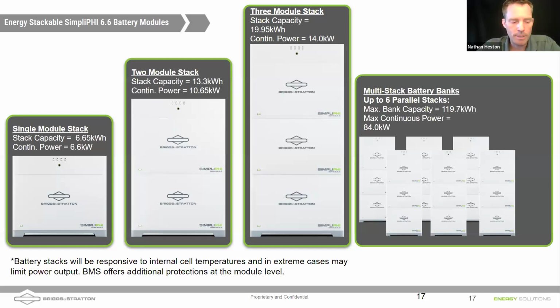Yeah, thanks Quinn, and I agree with you there. There are certain locations in a garage where you can mount the batteries without having protection from vehicle damage. But for instance, if you are mounting at the back end of the garage where the front of your car would be after you pull in, you either need parking bollards, or NFPA requires you to have a parking block similar to what you see in a parking lot, and that becomes a tripping hazard when your garage is empty, and it's got to be 54 inches from the wall. So yes, a great advantage of having a wall-mount battery is that you can have it up off the ground — I believe the number is 24 inches above the ground — and then you don't need these parking bollards. So that's a nice advantage.